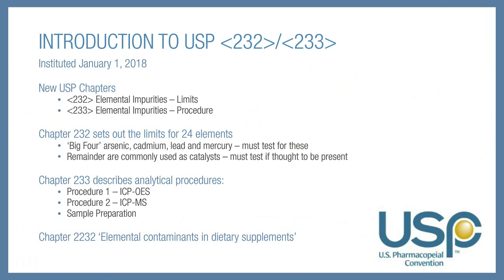The new USP chapters have been around for a number of years now. The new chapters consist of 232, which are the limits of elemental impurities, and 233, which is the procedure or actual methodology that allows us to reach the limits set forth in Chapter 232. Chapter 233 has two procedures for analysis, one for ICP-OES and one for ICP-MS. It also speaks about sample preparation. Chapter 2232 applies to elemental contaminants in finished dietary supplements and focuses on the Big Four.